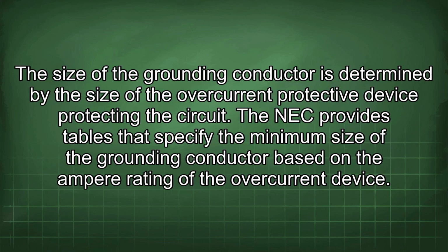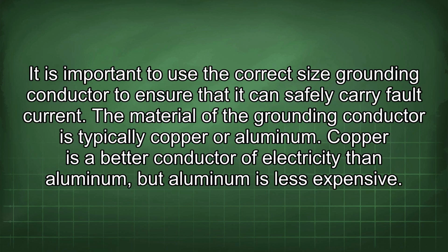The size of the grounding conductor is determined by the size of the overcurrent protective device protecting the circuit. The NEC provides tables that specify the minimum size of the grounding conductor based on the ampere rating of the overcurrent device. It is important to use the correct size grounding conductor to ensure that it can safely carry fault current. The material of the grounding conductor is typically copper or aluminum.